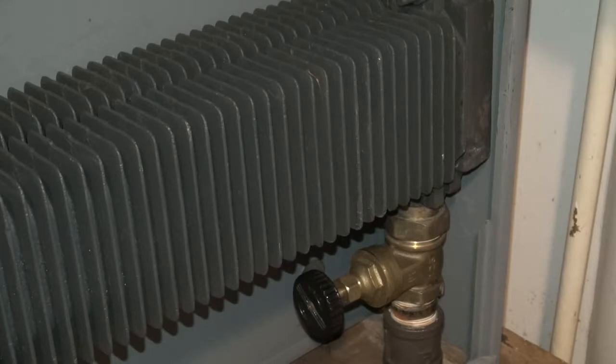Now, if you're dealing with a commercial grade boiler, with buildings and boilers the size of what I run at my job, you're going to notice that boiler will start to generate steam pressure within maybe 12, 15 to 20 minutes. Then you'll start to see the gauge finally pop up and you're getting a reading on the pressure gauge. But even with commercial grade boilers, you're not going to get 2 psi entering a radiator.